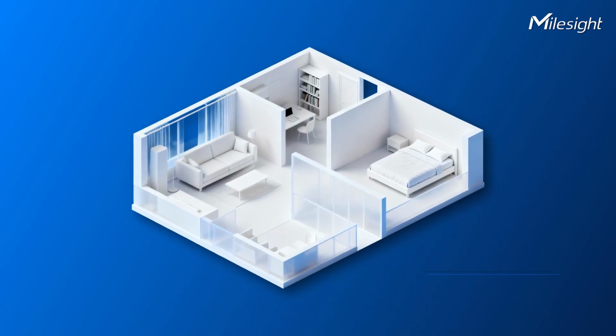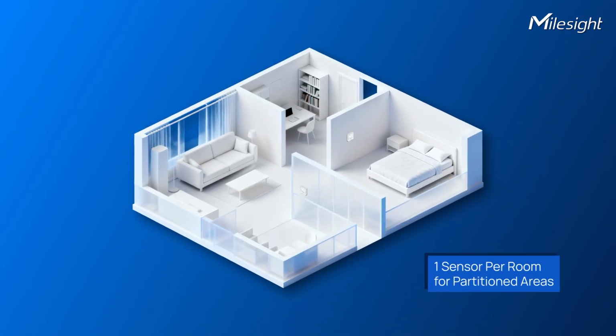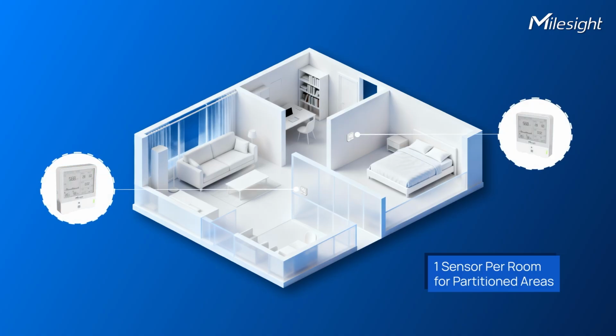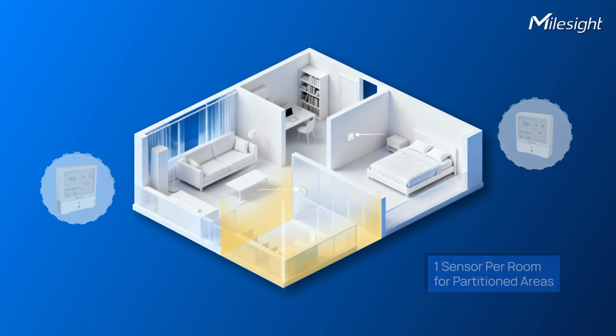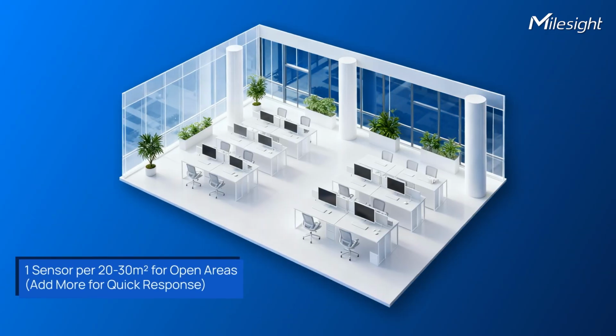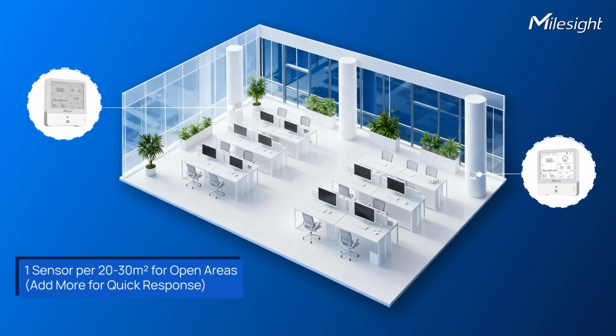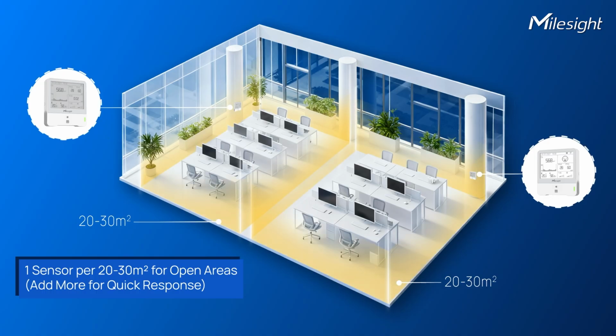Now that we know the ideal spot, how many sensors do we actually need? Let's discuss deployment density. A single sensor can only accurately detect a single point. It is recommended to deploy several representative points. For clearly partitioned rooms, such as company offices, one sensor per room is usually sufficient. For unpartitioned public areas, it is recommended to install one sensor every 20 to 30 square meters. For areas requiring quick response or important monitoring, the distance can be shortened. It is recommended to add 1 to 2 extra sensors.